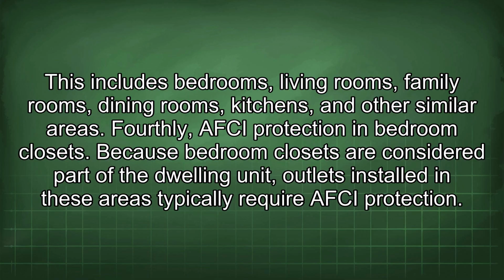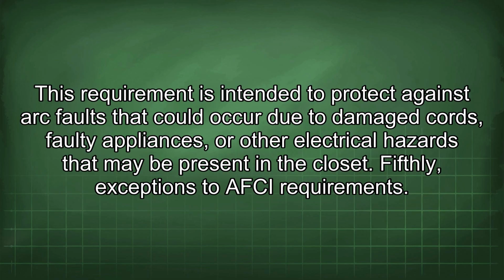Fourthly, AFCI protection in bedroom closets. Because bedroom closets are considered part of the dwelling unit, outlets installed in these areas typically require AFCI protection. This requirement is intended to protect against arc faults that could occur due to damaged cords, faulty appliances, or other electrical hazards that may be present in the closet.